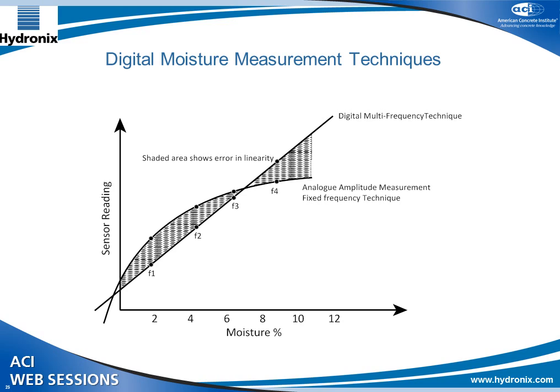Older sensors from before 2000 measured at a fixed frequency — what we call the analog or classic measurement technique. As moisture changes, the amplitude signal shifts non-linearly: the distance from f2 to f3 is much less than from f1. This means the moisture measurement for older sensors was a curve, making it very difficult to calibrate since each sensor would have a slightly different curve. Our new sensors use a digital multi-frequency technique that produces a linear output, making calibration very simple — you just need to find two or more points on the line to define it.